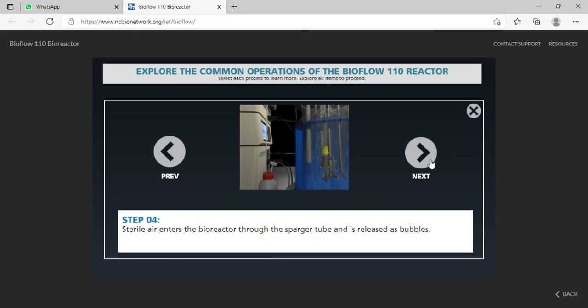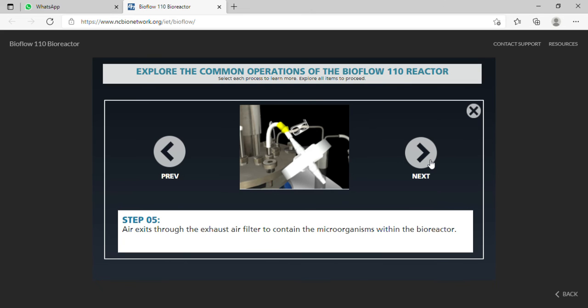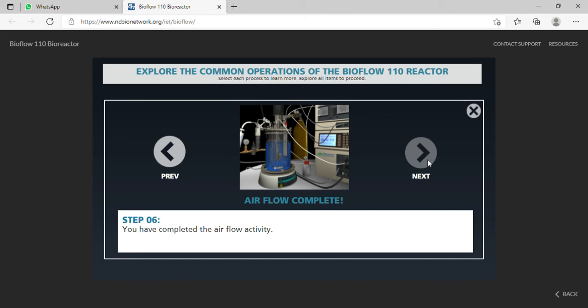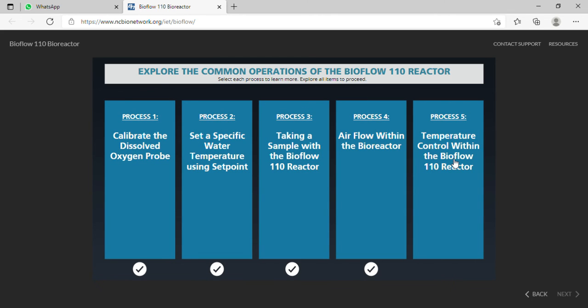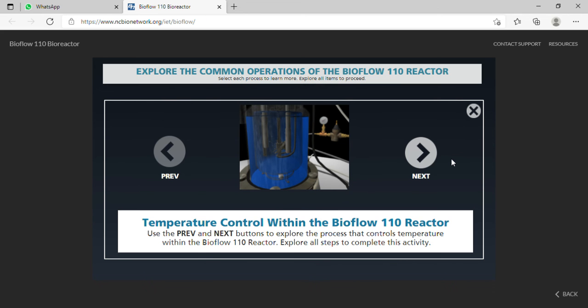Step 4. Sterile air enters the bioreactor through the sparger tube and is released as air bubbles. Step 5. Air exits through the exhaust air filter to contain the microorganisms within the bioreactor. Step 6. You have now completed the airflow activity. Process 5 is the temperature control within the Bioflow 110 reactor.